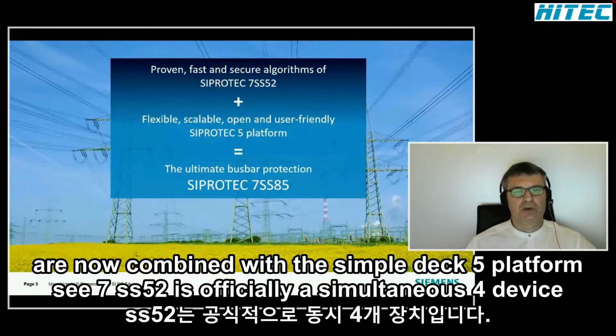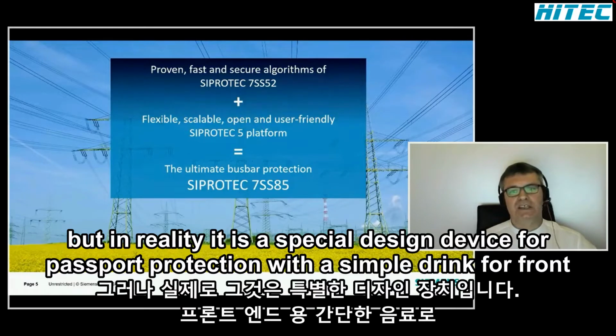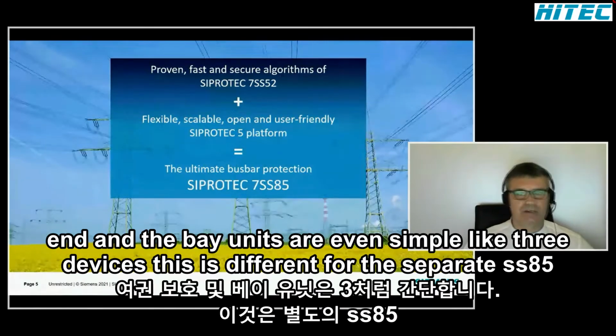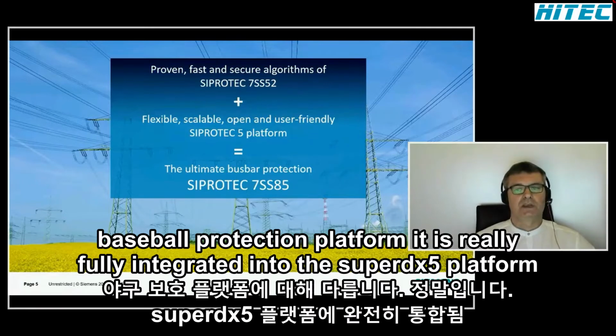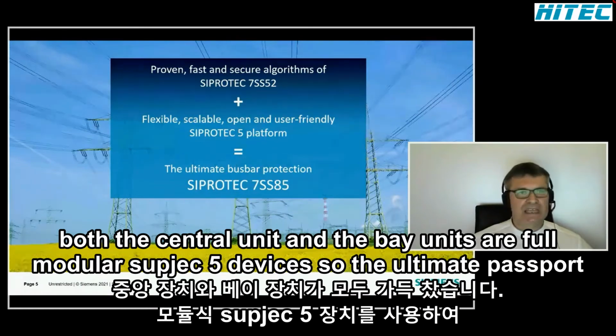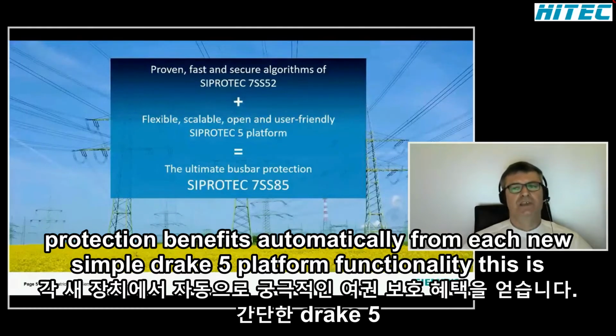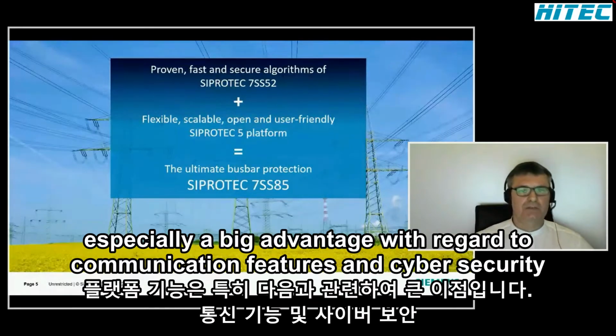The 7SS52 is officially a SIPROTEC 4 device, but in reality it is a specially designed device for busbar protection with a SIPROTEC 4 front end, and the bay units are even SIPROTEC 3 devices. This is different for the 7SS85 busbar protection platform. It is really fully integrated into the SIPROTEC 5 platform. Both the central unit and the bay units are fully modular SIPROTEC 5 devices. So the ultimate busbar protection benefits automatically from each new SIPROTEC 5 platform functionality. This is especially a big advantage with regard to communication features and cybersecurity.